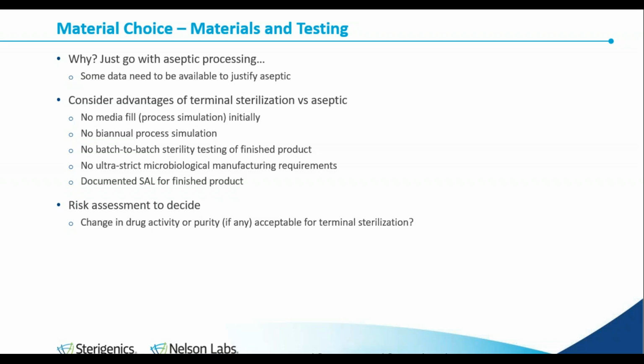Really no ultra strict microbiological manufacturing requirements, and you do have an actual sterility assurance level for the finished product. With aseptic processing, there is no SAL that can be applied, nor a contamination rate. There really is no output of a process simulation that gives a numerical value. The process simulation just tells you that the process is validated, but no output as a result of that.